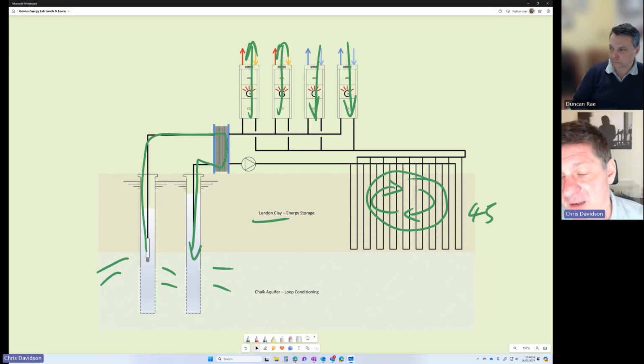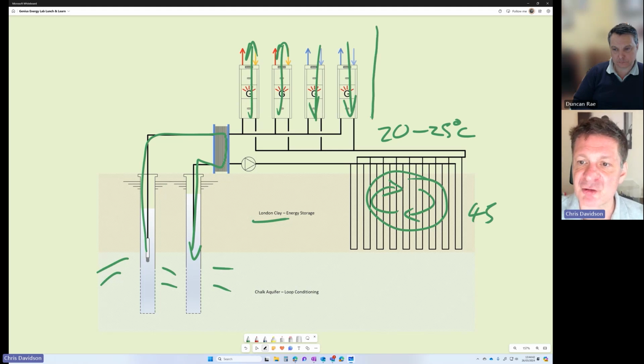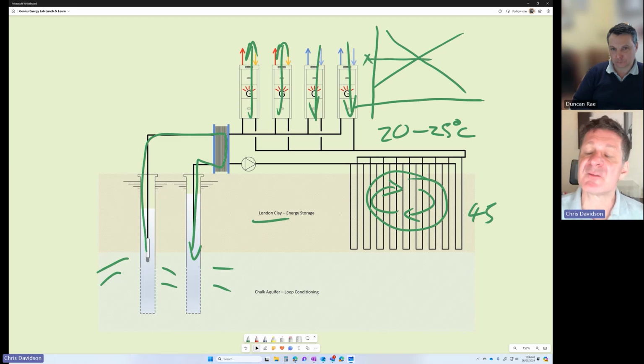Now, the magic number for the particular heat pumps involved here is 20 to 25 degrees. So we're actually managing that ground loop temperature in that 20 to 25 degree regime. And that just happens to be the point at which the cooling efficiency and the heating efficiency crosses over for that type of heat pump. So we're maximising both heating and cooling efficiency.